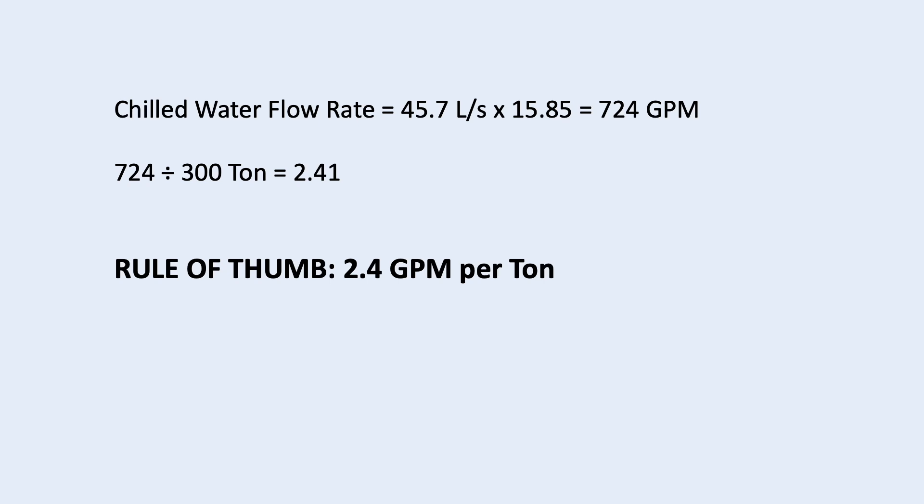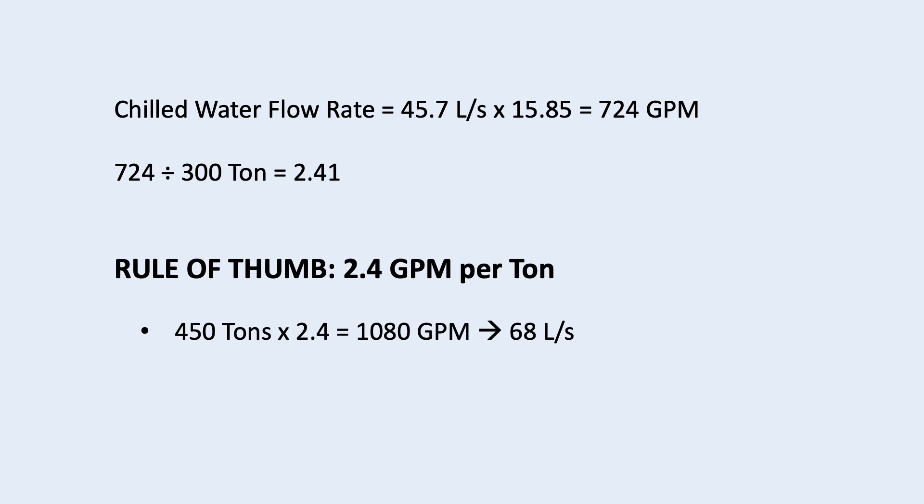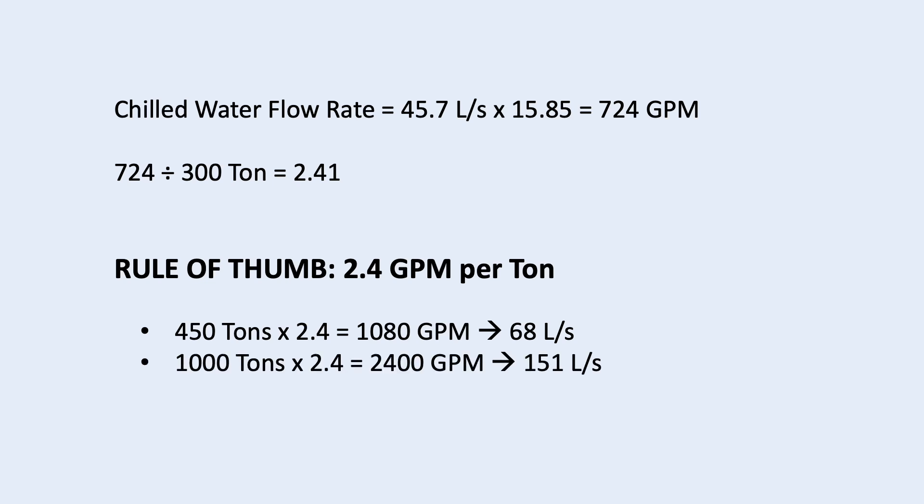We just use the rule of thumb of 2.4 GPM per ton. For example, 450 ton times 2.4 is 1080 GPM. Divide this by 15.85, we will get 68 liter per second. Another example, if it is 1000 ton multiplied by 2.4, then you get 2400 GPM.